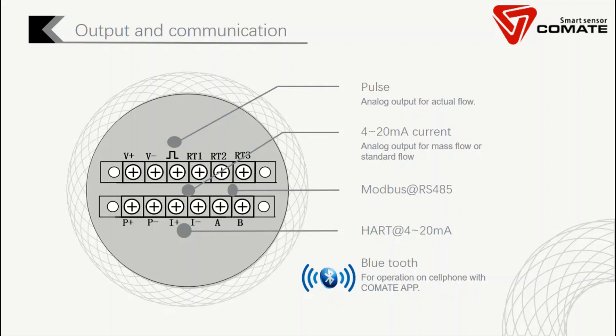For output and communication, we provide pulse and analog output. We have 4 to 20 mA current output. We have Modbus. We also have HART integrated on the 4 to 20 mA. We also have Bluetooth technology, which is quite unique in the market. With this Bluetooth communication, customers can use the Comate app installed on their cell phone to communicate with the flow meter to read or operate it, making setup much easier.